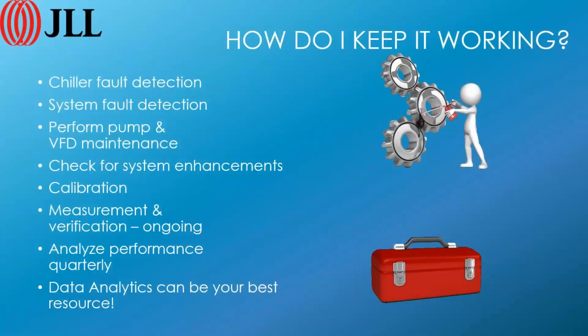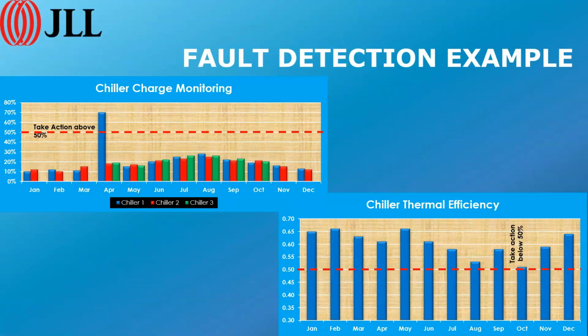Here's another question. Can you increase the plant efficiency by stripping more heat from the condenser water feed through a heat exchanger to some process heat in the building? Or will that add too many competing variables and not be worth the investment? Sure. If you've got a constant heat sink, that's kind of clever. If you've got a constant heat sink, then sure, why not? No reason why not. Yeah, I think that's really clever. Okay. Yeah, so that's right. So then you're just saving on tower fan energy, kind of, right?